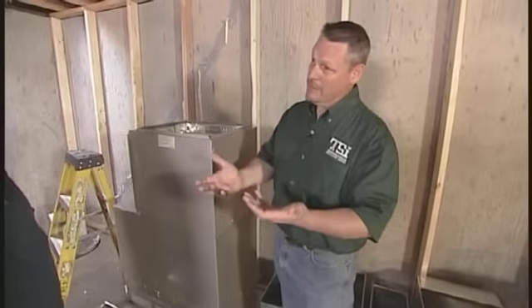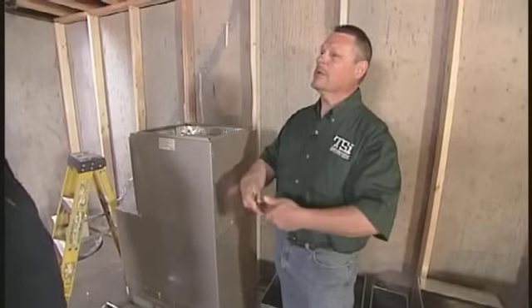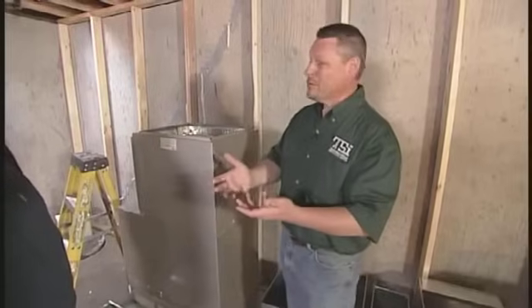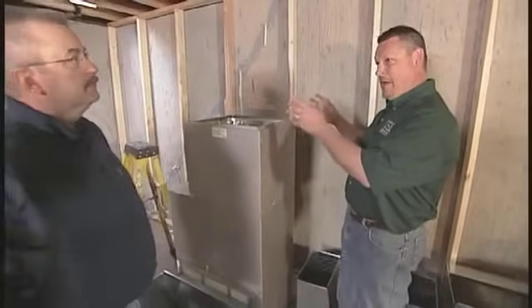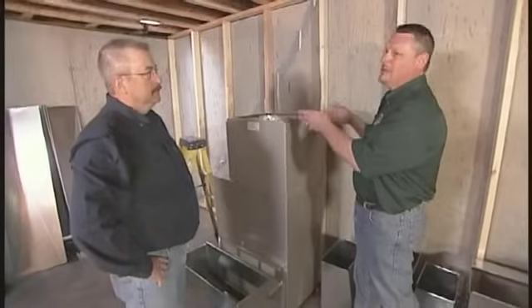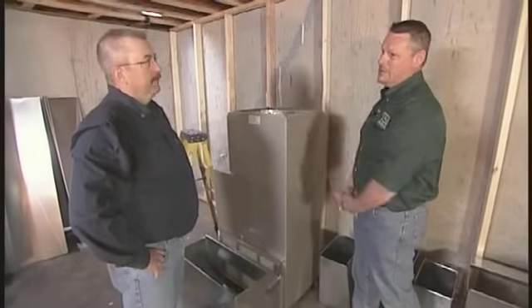If you size it too small, they're going to have inadequate heating and cooling. If you size it too large, you're not going to have enough volume when you get to the other end, where you get the velocities coming out of the ductwork. So it's a critical measurement and calculation that's done on every home to ensure you have the right size ductwork in each location.